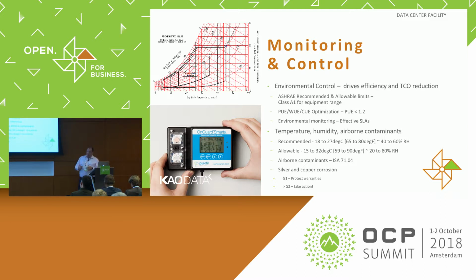The other thing we do to help maintain customer warranties, especially with traditional servers, relates to the move away from lead solder to silver solder - there's a risk of contaminants in the air, especially if you're using external air to cool the data center. We actually use recycled air through the indirect system, but you still have to provide some fresh air into the data hall since we've all got to breathe when we go in there to maintain it. ISA 71.04 really constrains what we need to do in terms of meeting contaminant pollution limits.